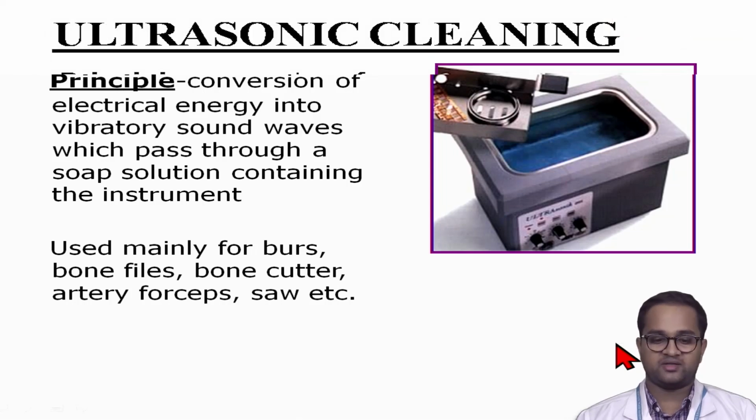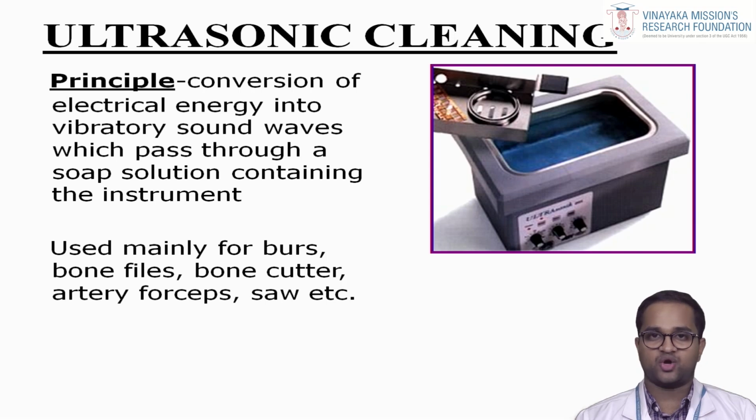Coming to ultrasonic cleaning, the principle is the conversion of electrical energy into vibratory sound waves, which pass through a soap solution containing the instrument. It is usually called a biosonic solution. It is used mainly for burrs, bone files, bone saws, artery forceps, saws, etc.